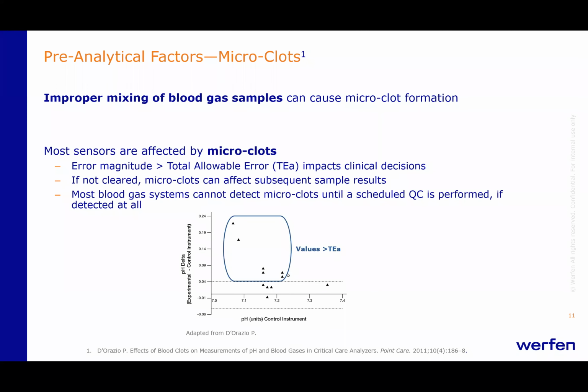If you take a look at the graph, the way this study was done was that they treated samples to give values along the whole array of measurement values for all the analytes. So they would tonometer, that's where they add gases to give varying values for pH, or for PCO2 and PO2, or they would alter the pH, electrolyte values, metabolite values on samples. Then they would split those samples, and one set of samples would be heparinized adequately, and the other set of samples from those same syringes would have clot producing chemicals added to them. Then they would compare the results on two sets of analyzers.